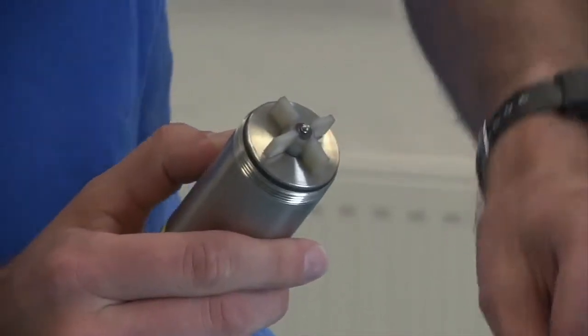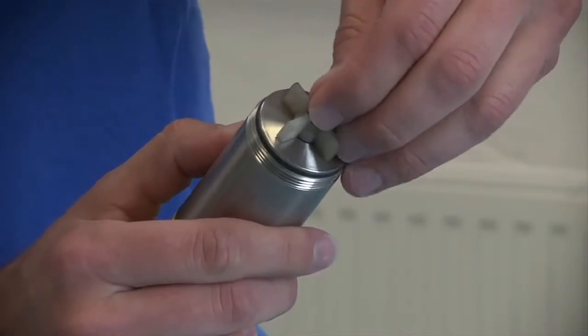Replace the upper thrust washer, the o-ring, and then replace the impeller cap.